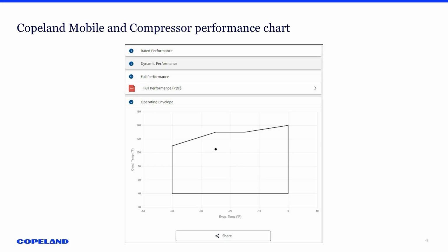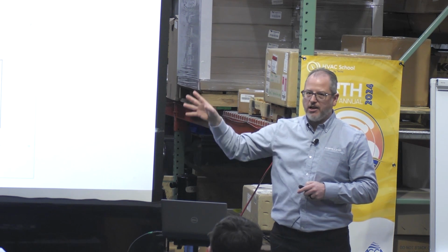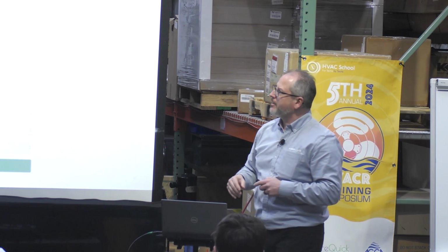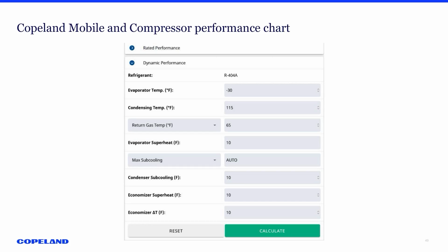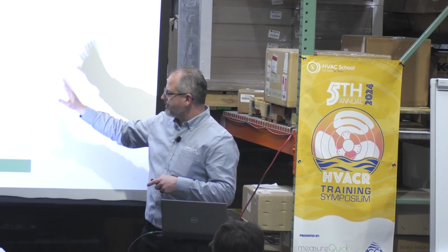At those rated performance, we're at -25 and 105. So that's where that dot is, where it's running right now. Okay? So now I'm going to change what it's running at. I just went to the dynamic performance, and I changed it to -30 degrees and a condensing temperature of 115. Just so we can see all the other information, I kept the same as now, and I just hit calculate.